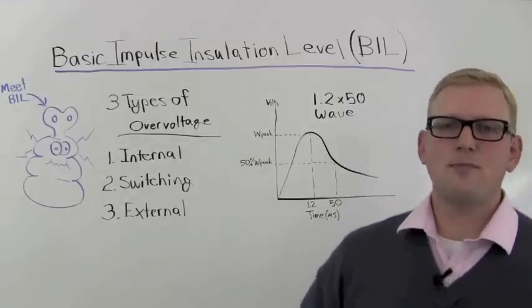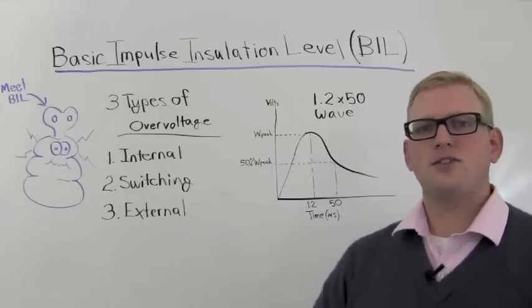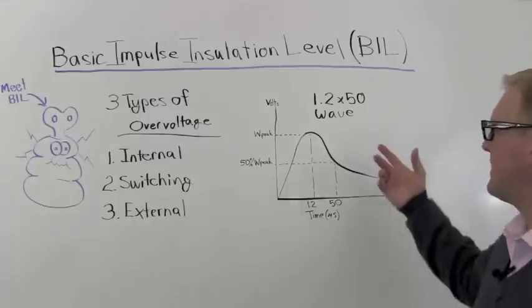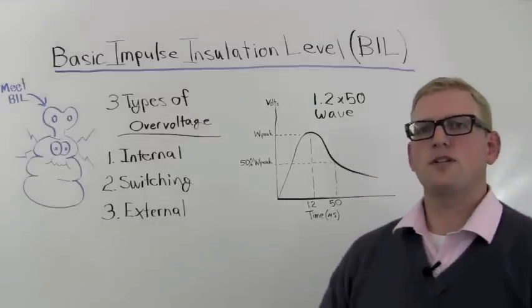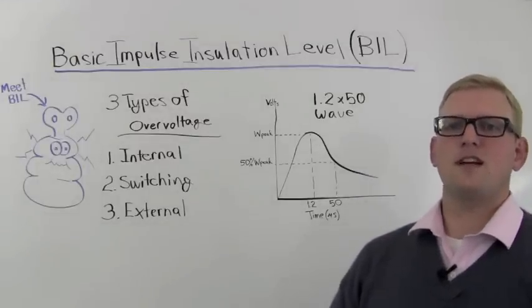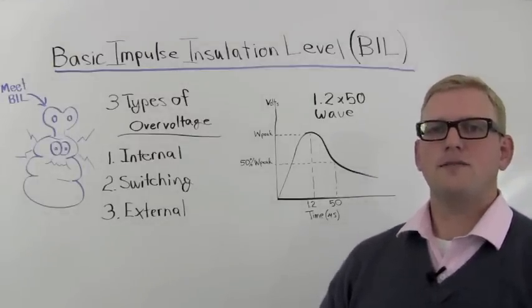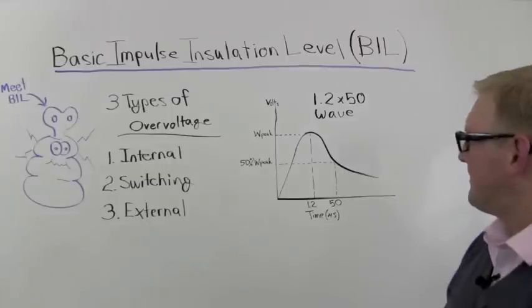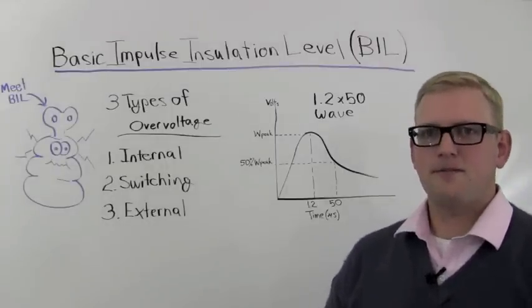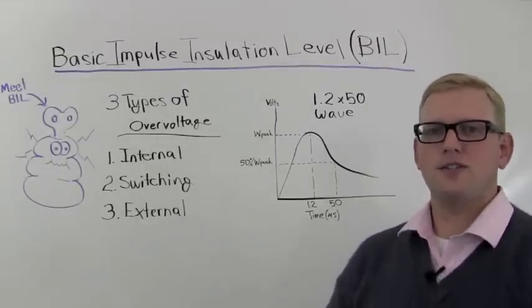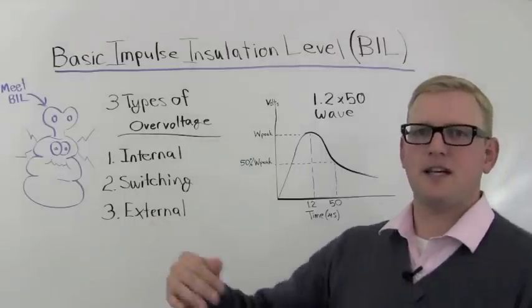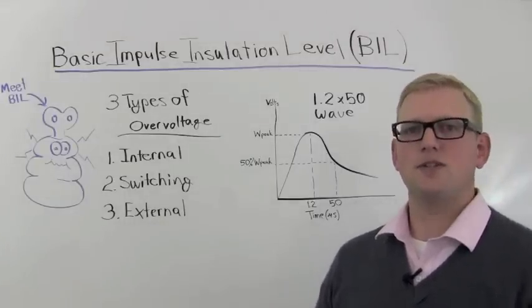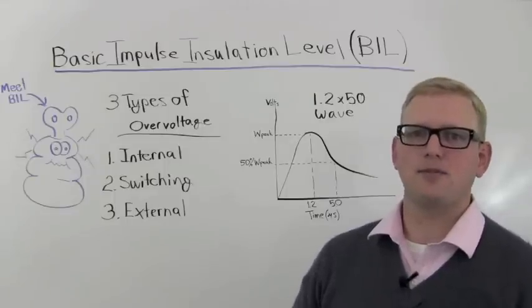To give you an example of what a surge or transient looks like in terms of a wave, I have illustrated here an example of a 1.2 by 50 wave, which is the standard waveform of a transient or voltage surge. It has a very steep front, and the numbers come from the time at which the wave peaks and subsides to 50% of peak.